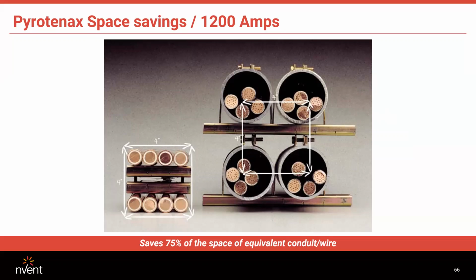But if you have MI cable and you have the right circumstances for voltage drop, say it's 300 feet or less at 480 volts, you could use 2 runs per phase of our 500 kcmil and fit the cable in there. So it's a good thing for both engineers and contractors to keep in mind. In fact, quite a few of our non-fire rated applications get initiated by the contractor, because the engineer might not be aware of how dire the space situation is out there. The contractor brings it to the attention of the engineer, and the engineer's like, oh, of course, yeah, sure, MI cable, great. But it's a good thing to keep in the back of your mind.